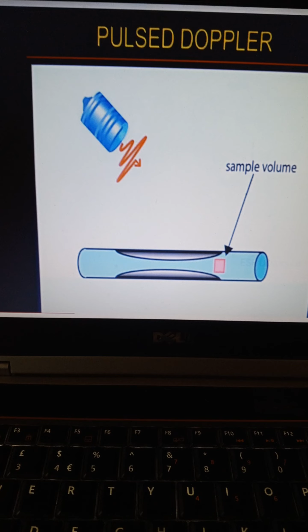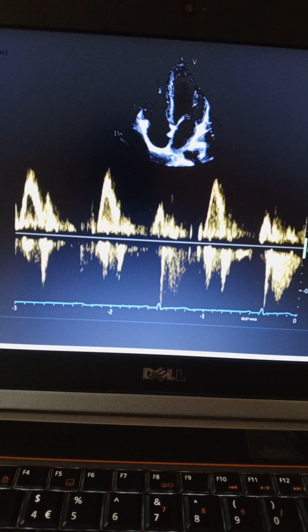For this one, the disadvantage is you cannot measure high velocities. So this one is for normal flow. For normal flow, we use pulse wave Doppler. This is a presentation of the pulse wave Doppler at the mitral inflow signal, and it shows positive flow above the baseline and negative flow below the baseline. This is the four chamber view when we're doing an echo.